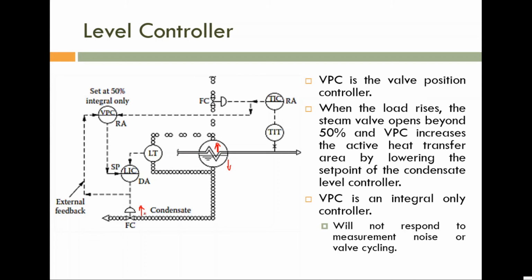Okay, this is a normally closed valve, so we can open this control valve by increasing this control signal. By increasing this control signal, we can open the control valve. So this control signal is given by LIC, whose set point is this one and measurement is this one. Okay. So this measurement, this liquid level, will decrease only if you are opening this control valve.